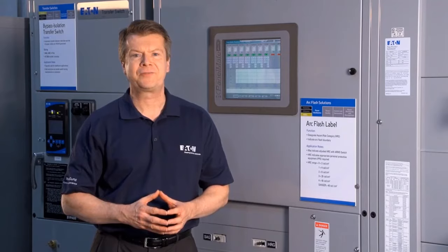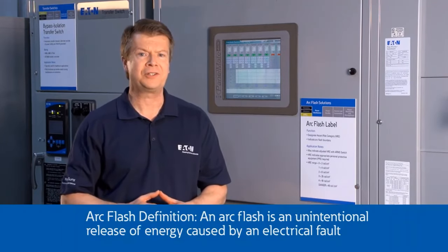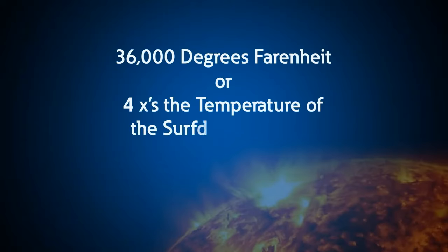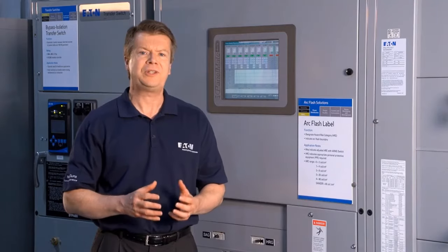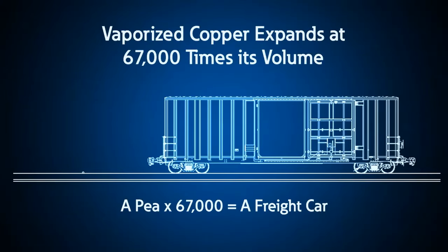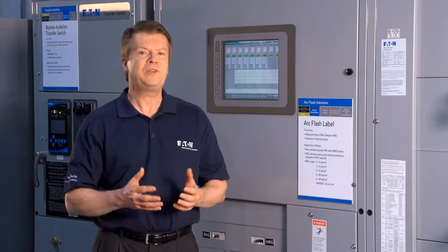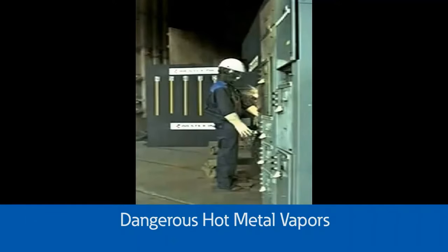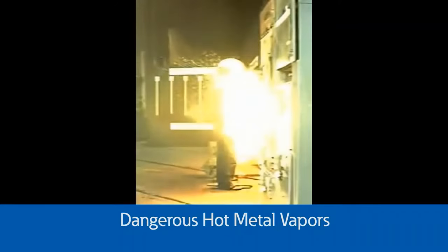How can you ensure that you're doing everything you can to keep your employees safe? Here at the Power Systems Experience Center, you can learn about arc flash safety and the solutions that exist to keep you and your people safe. So what is an arc flash? An arc flash is an unintentional release of energy caused by an electrical fault. An arc flash event can reach temperatures of 36,000 degrees Fahrenheit, or 4 times the temperature of the surface of the sun. During the arc, copper can expand at 67,000 times its volume, very much like an explosion caused by dynamite. And if you're as startled as you would be in the case of an arc flash event, you would quickly inhale and breathe in that vaporized copper.